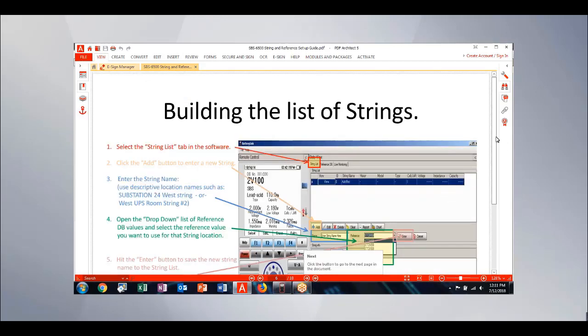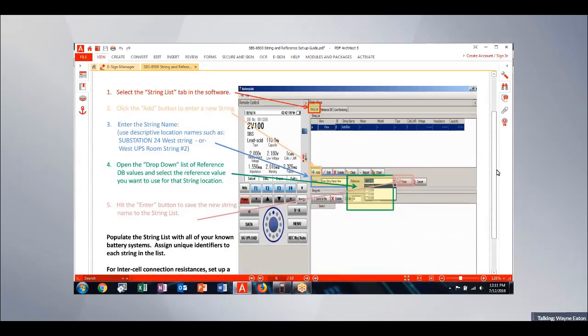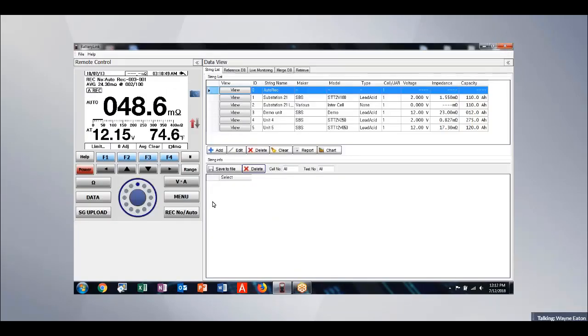On the string list, this is going to be a list of all of the locations where you're going to be taking measurements. So substation 1 through substation 999. The string list is built 1 entry at a time, simply by entering the name of the location that the measurements are going to be taken at, and then selecting the reference value from the drop-down list next to it. And then just press enter, and it's going to save that entry.